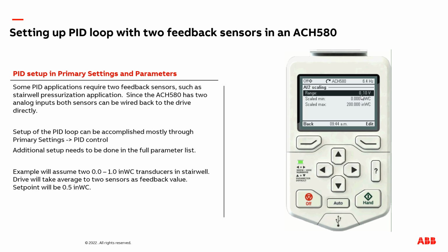Now, in my setup, I have 0 to 10 volts as my feedback transducer, and I don't have 0 to 200 inches of water column. I have a 0 to 1 inch of water column. So I need to adjust the maximum setting here for the range of the transducer. So go from 200 to 1. So now I have min is 0 inches of water column, and my max is 1 inch of water column. Then back out of here.